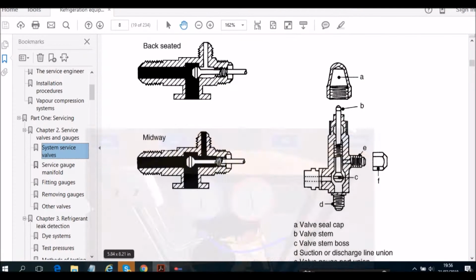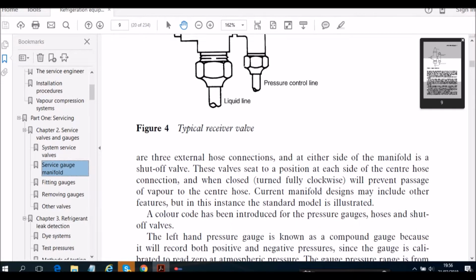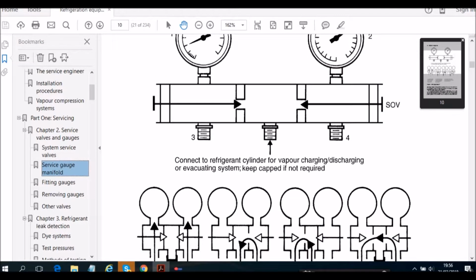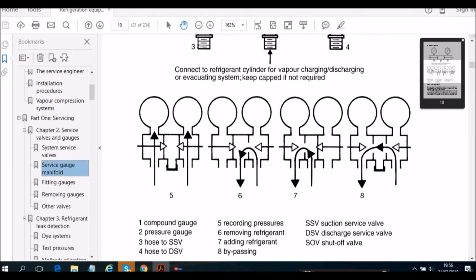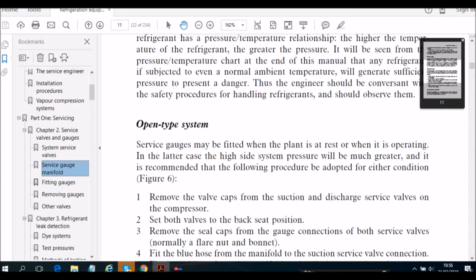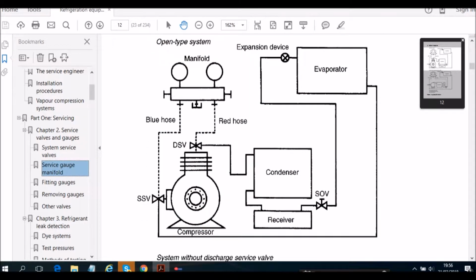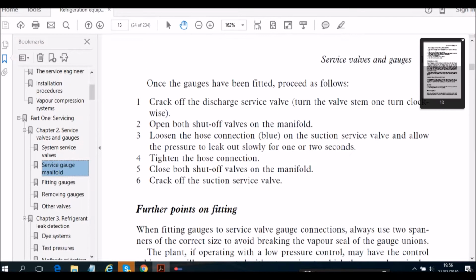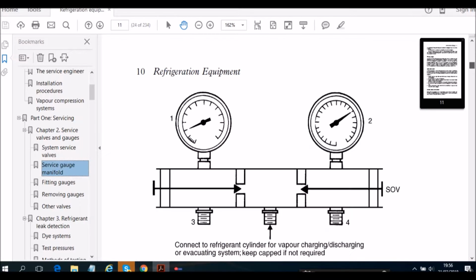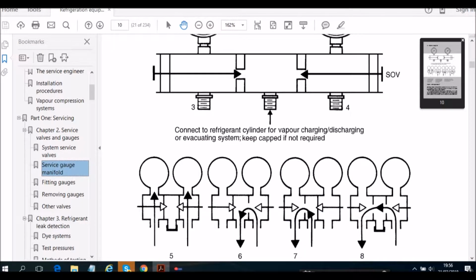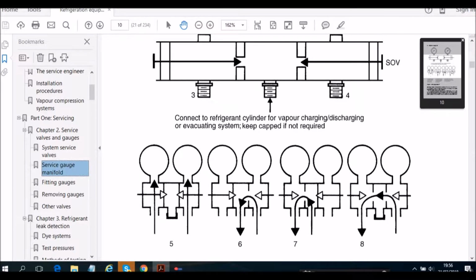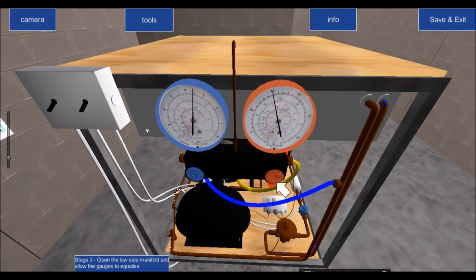And by doing that, if we go back to our service gauges, where was page 10 is what I'm looking for. So our service gauges, by me opening, I've effectively... There are better pictures, I think, further down. Sometimes there are better pictures, but it's not there at the moment. Okay, apologies, I'll just go back up. So by opening it, I've allowed the refrigerant to go from my red hose line into my service area here. So now the high side refrigerant is going to cross into this service area. So I have refrigerant in my yellow line, and refrigerant coming from my red hose into my manifold. So the refrigerant is here.